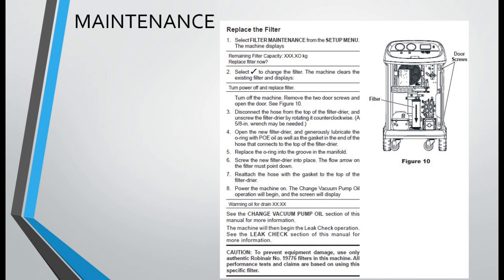Replace the filter. 1. Select Filter Maintenance from the Setup menu. The machine displays remaining filter capacity, XXX.X kilograms. Replace filter now. 2. Select the check mark to change the filter. The machine clears the existing filter and displays: Turn power off and replace filter. Turn off the machine. Remove the 2 door screws and open the door.